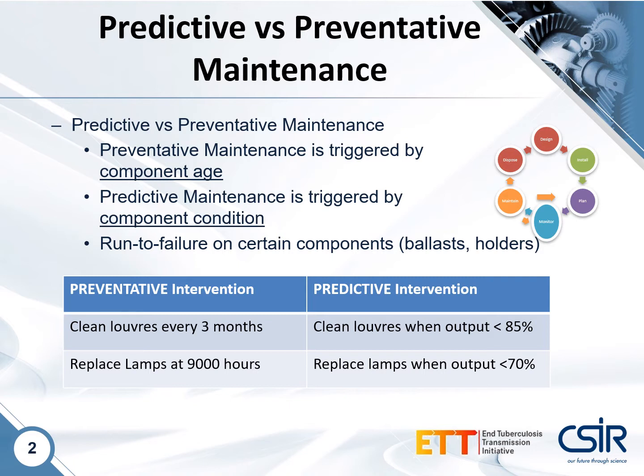This is not to say that run to failure strategies for certain components is not appropriate. For instance, your ballasts or your lamp holders could be kept in stock and replaced as needed and on failure, because monitoring and predictive replacement of these components is significantly more difficult. The table here shows the difference between some of the interventions of predictive versus preventative maintenance strategies.